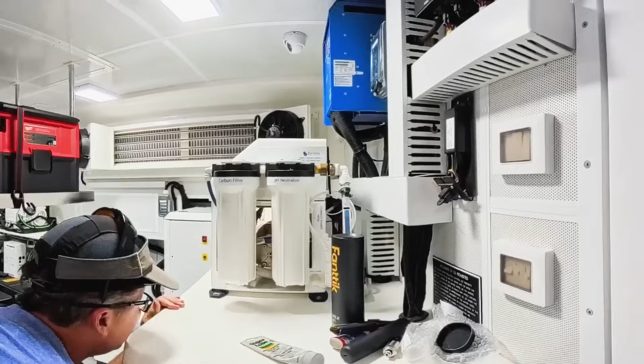Manual control, okay, I'm going to be turning on the booster pump. It's going to make a little noise. Yeah, that water probably came from when I took the fitting out. So we've got the low pressure feed pump on and running. All right, here we go, now it's going to get louder. Take a video and send it to the client. Inlet and outlet, we don't have product flow or brine flow yet, but yeah, she's running. Here's the old one.